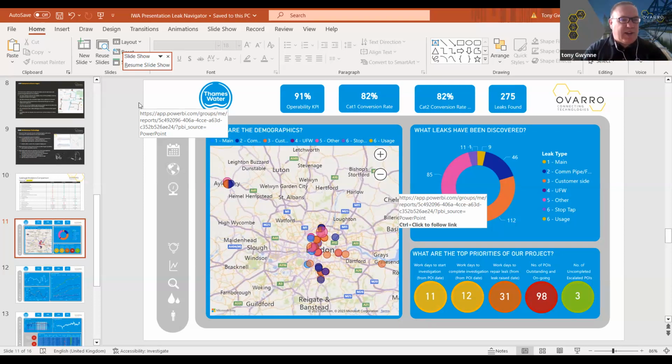So we've had POIs that have found 2 or 3 leaks. When the technician expands his vision on site, he might pick up 1 or 2 leaks. But overall, we're probably taking you to 1 leak initially, and then obviously fix that. And then actually another leak will be visible then, and the correlators will work pretty quickly straight away to show that. So will we miss leaks? I think fixed network loggers probably can miss leaks. But obviously this is a long-term vision of 5 years of monitoring a DMA. So you would hope within the first probably 3 months, all the leakage that was there in the first place would be picked up by the logging.